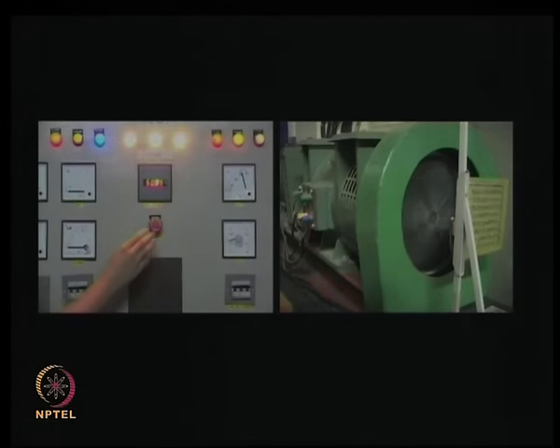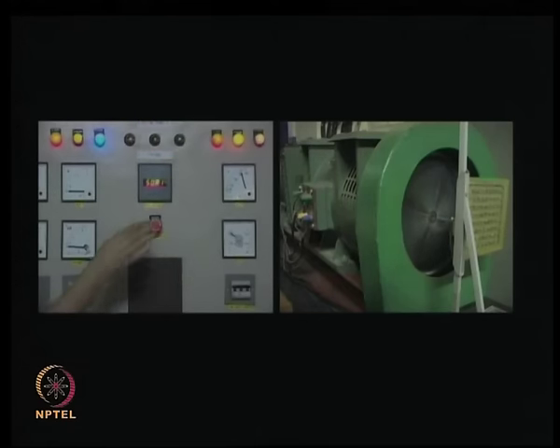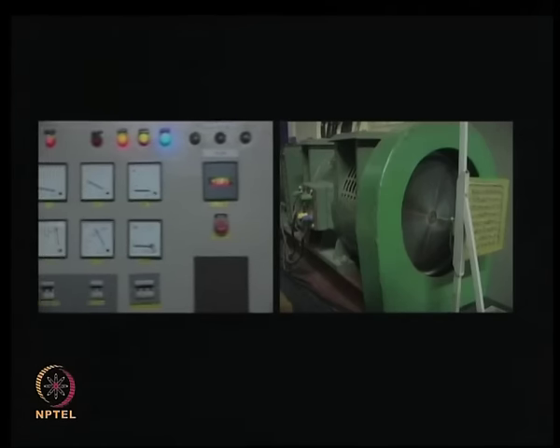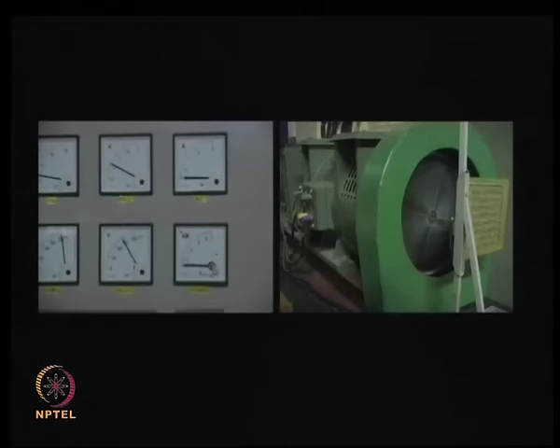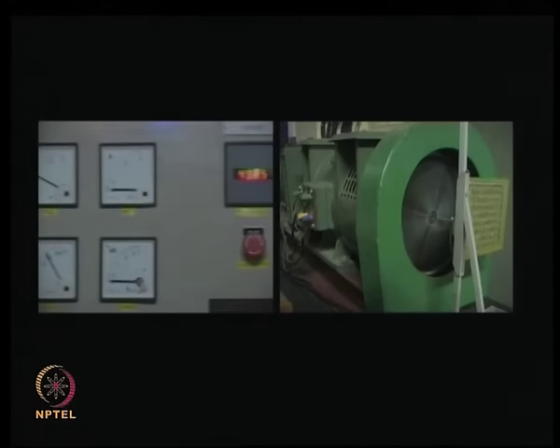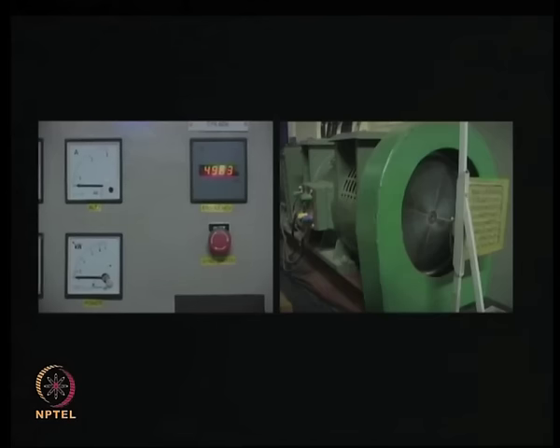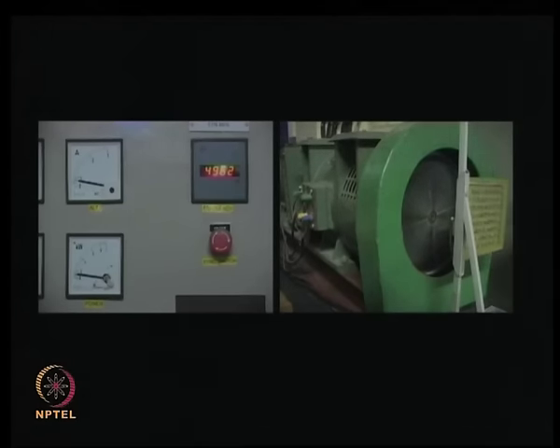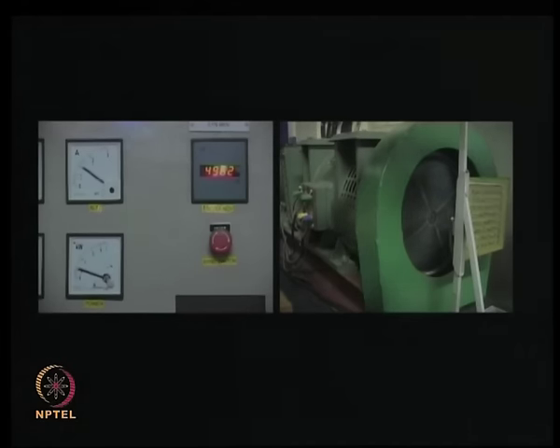We control the speed of the armature by armature voltage control, and we get the speed almost equal to that of the grid, and we synchronize, and you will notice now that the cross mark is absolutely stationary. Once we have synchronized, we can feed power into the grid by increasing the power output of the synchronous machine. This is done by actually increasing the power input to the DC shunt motor. So, you see how the power is increased, and simultaneously you will find that the cross mark is moving.